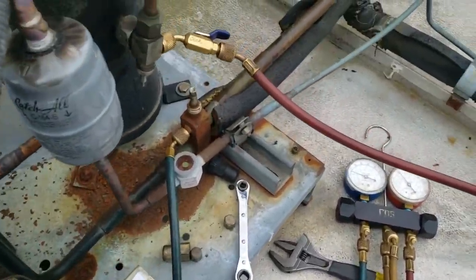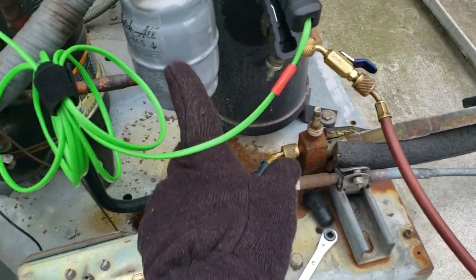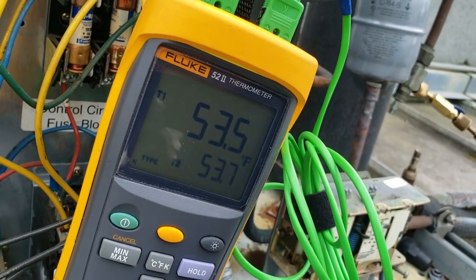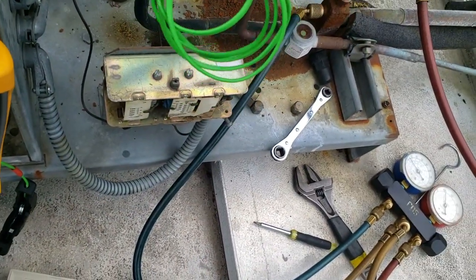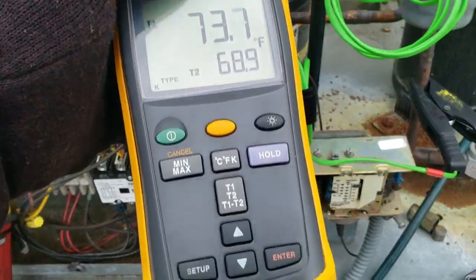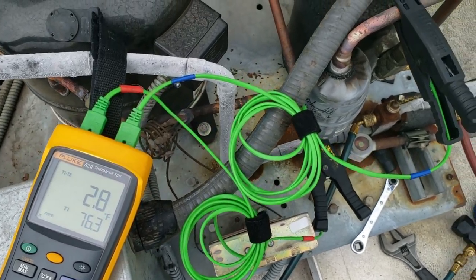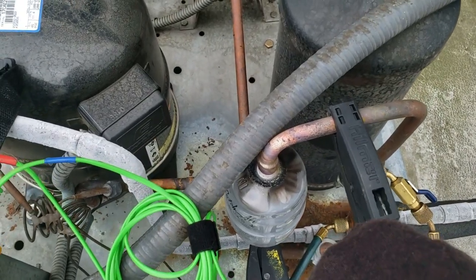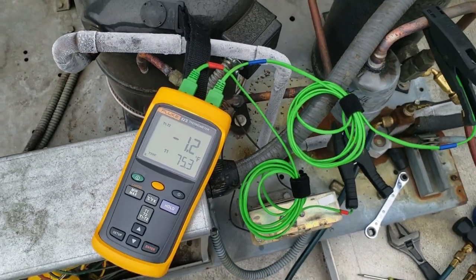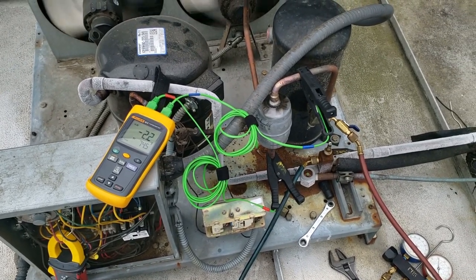We'll let it run for a little bit and see if it starts acting up again. Thinking more about it — since we had an empty sight glass, the only thing that would have intercepted it would have been our filter dryer, which was just recently changed. Should be able to clamp on here and any temperature difference should tell us whether or not this thing is plugged up. It's been running for a while and we got a 2.8-degree difference. Nice and tight — there it goes again.